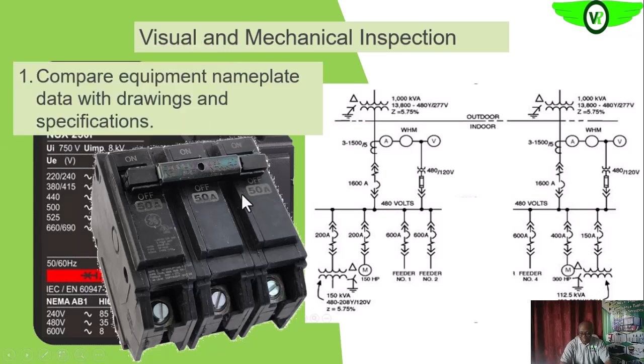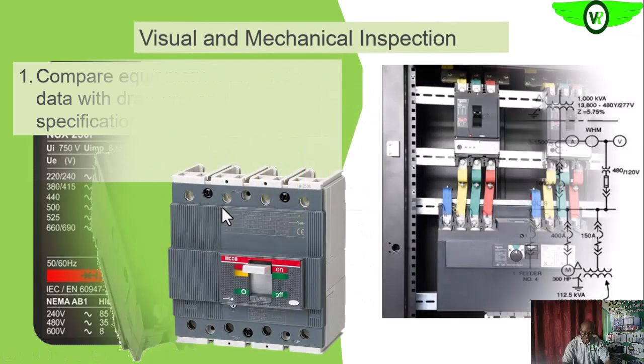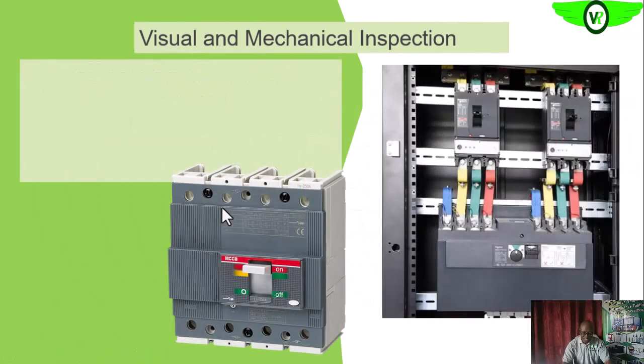This is the current rating of the circuit breaker. So a circuit breaker like this, suited for a 415 environment, can be used there, but it cannot go into circuits rated at 200 amps or 600 amps, for instance. Basically, these are the things you look out for to be sure the circuit breaker matches and will work in that particular circuit.